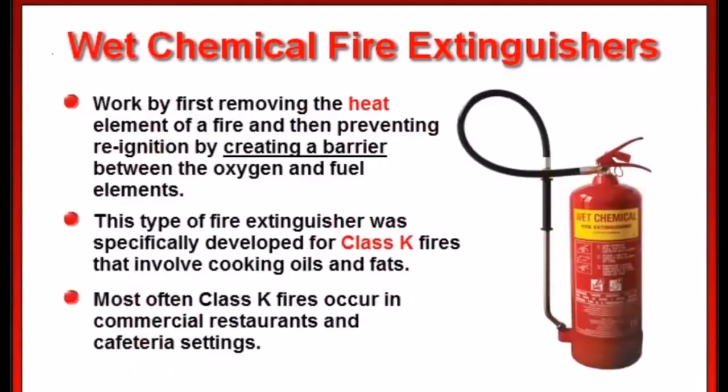Wet chemical fire extinguishers work by first removing the heat element of a fire and then preventing re-ignition by creating a barrier between the oxygen and fuel elements. This type of fire extinguisher was specifically developed for class K fires that involve cooking oils and fats. Most often, these class K fires occur in commercial restaurants and cafeteria settings.